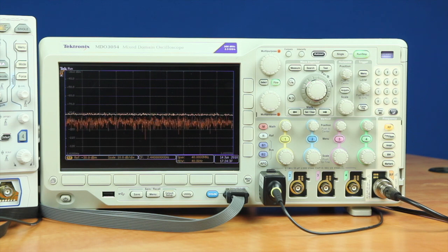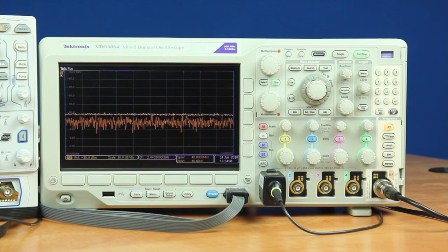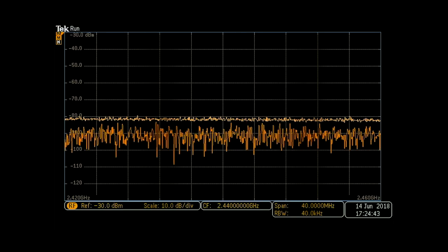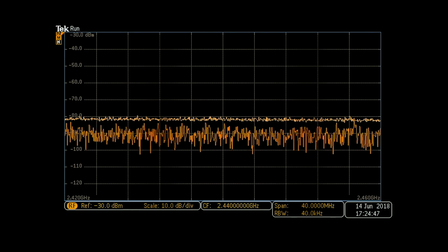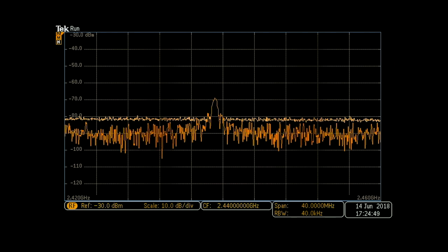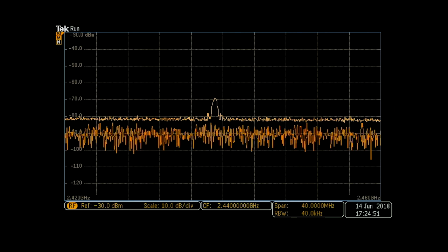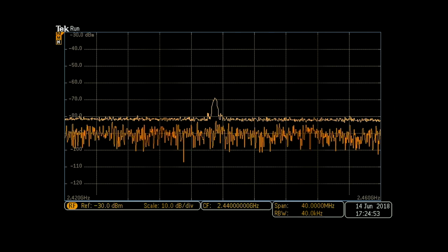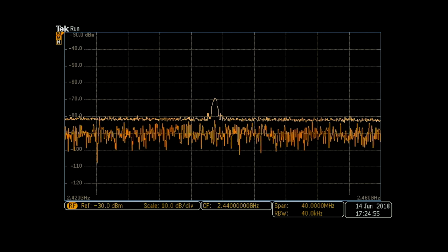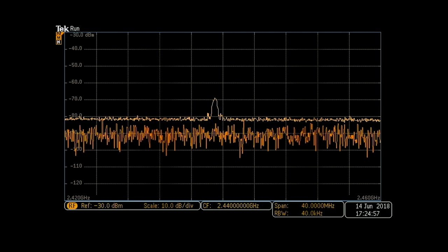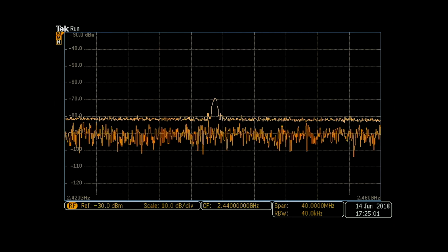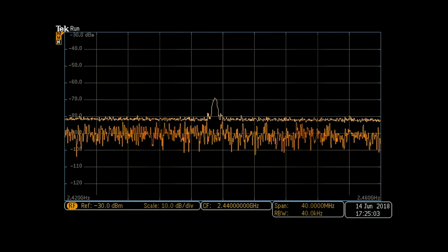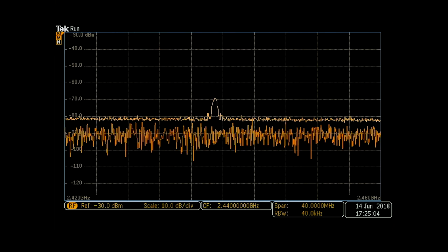We're trying to capture that 2.4 GHz RF output. It's a short duration pulse that's happening about once a second, so we haven't captured it yet. Because of the analog bandwidth here you have a great capture bandwidth — there we caught one. But there's a signal moving around in this band of short duration, so because of the short duration it's difficult to capture and analyze on the spectrum analyzer within the MDO 3054. Once we capture it, hopefully we can then analyze it further.